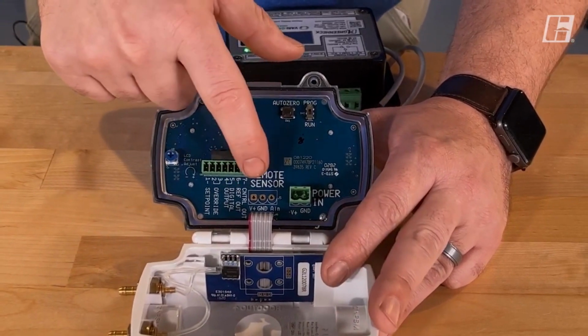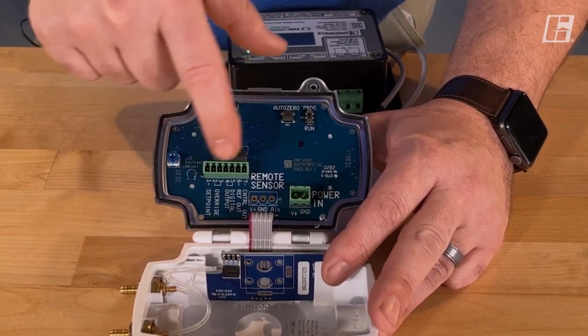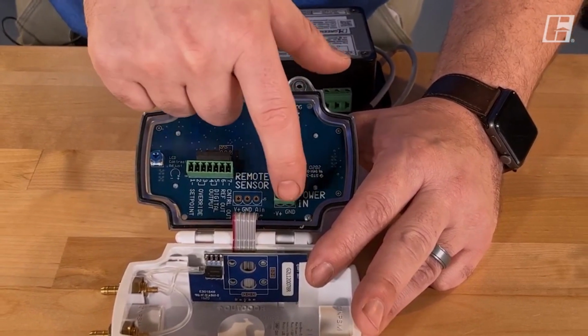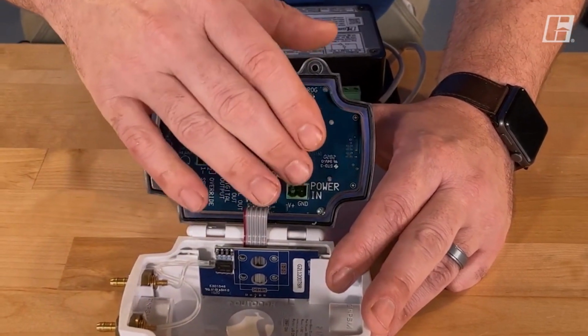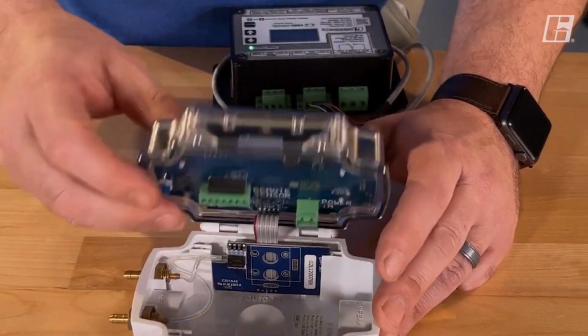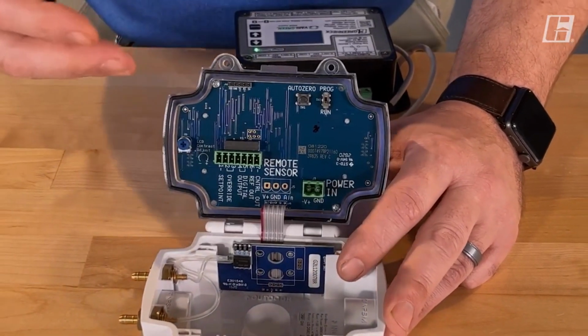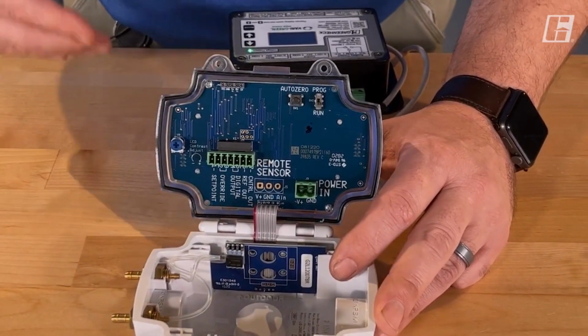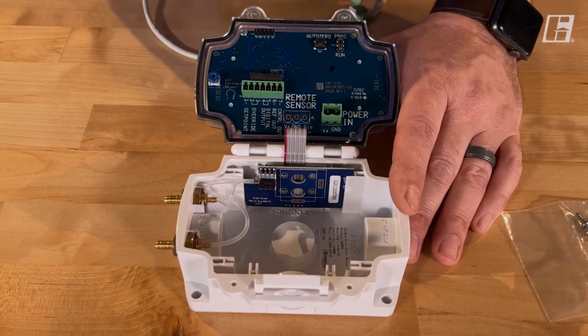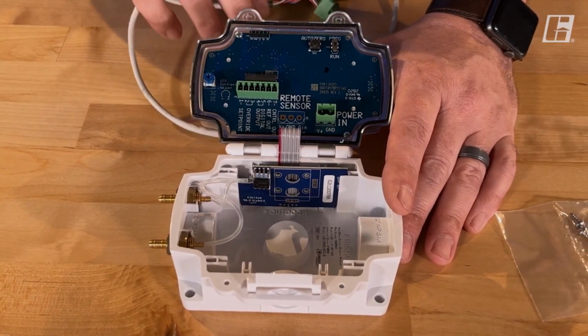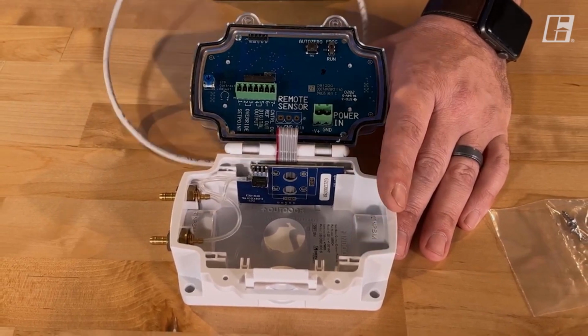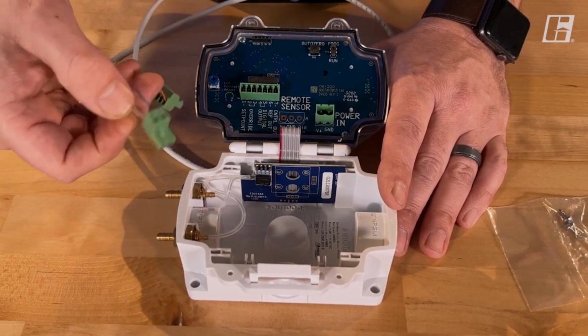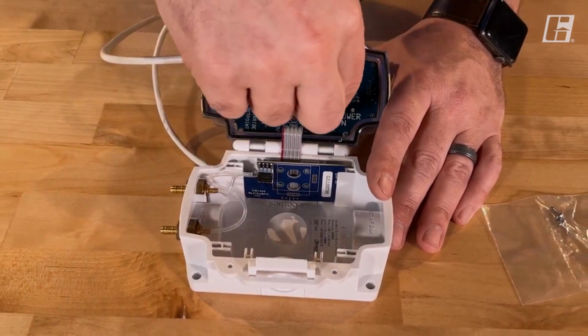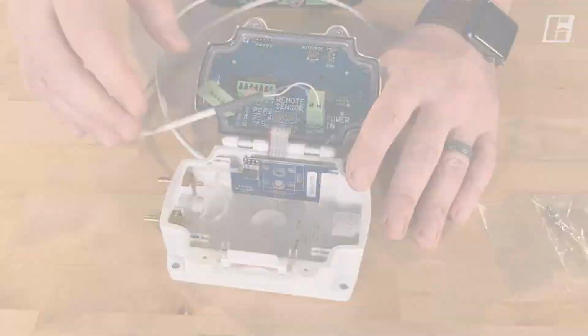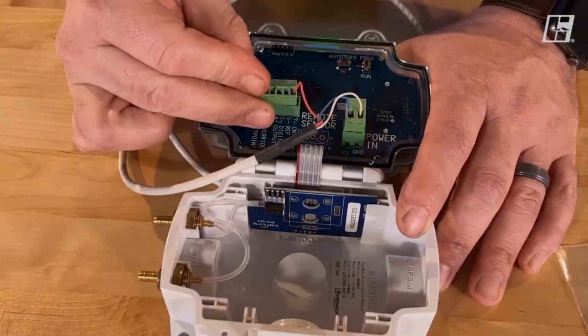We have our 7 terminal pins here and our power here. So this whole control is powered off of 24 volts. Typically, that 24 volt power for this control is provided by either a Vari-Green transformer or a Vari-Green HOA control. So what we're going to do now is I'm going to take a wire. I happen to have a Vari-Green HOA controller here, and it has allowed me to grab the 24 volts and the common. We'll simply plug those in that port. So this next terminal strip, we'll go ahead and plug that in.